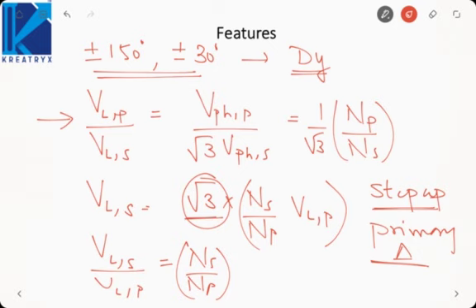So remember, if ever you want to get an EMF which is sinusoidal, you need one of the windings to be delta connected, because delta will allow the flow of third harmonic magnetizing current and EMF will turn out to be sinusoidal. So if primary or the secondary winding is delta connected, the problem of third harmonic EMF is resolved. So these are the features of the delta star type of transformer. What you have to remember is the phase shifts plus minus 150, plus minus 30, and it can be used as a step up transformer because of the higher secondary voltage.